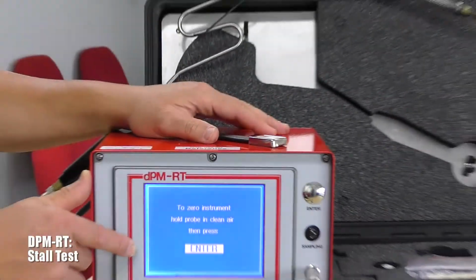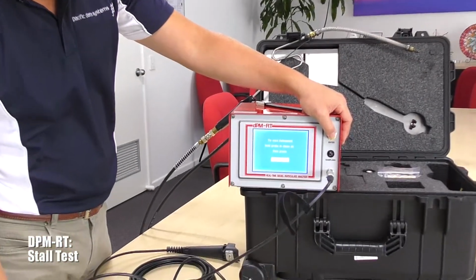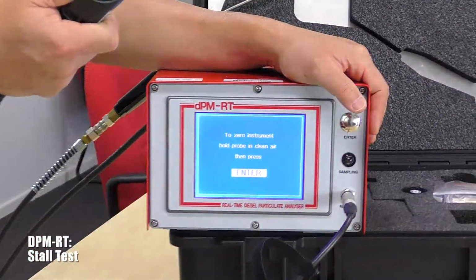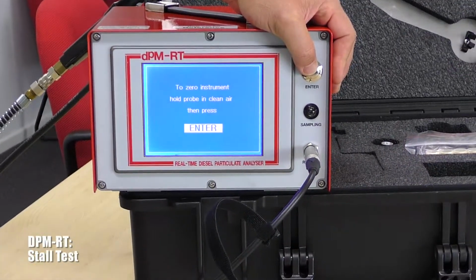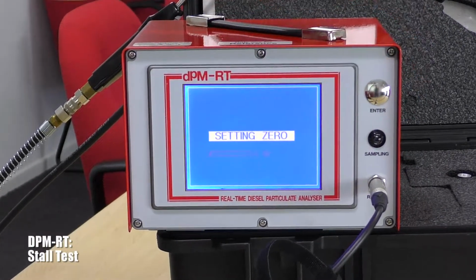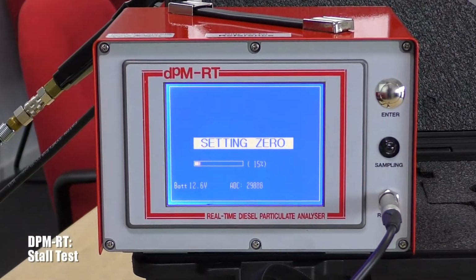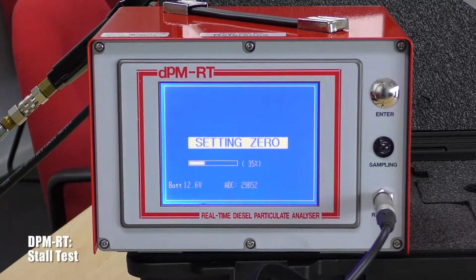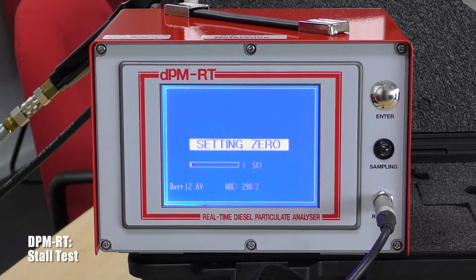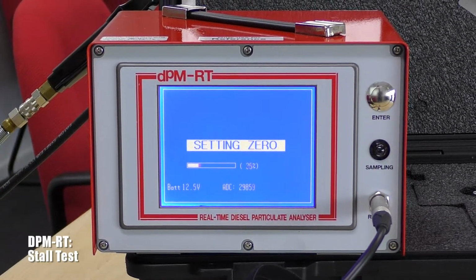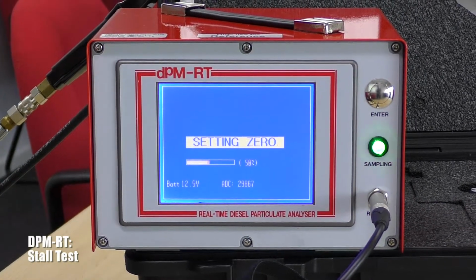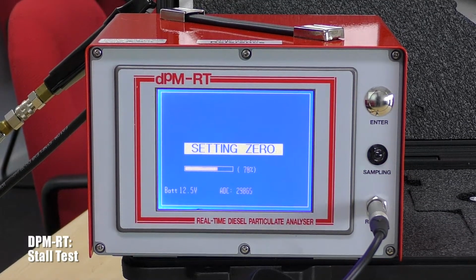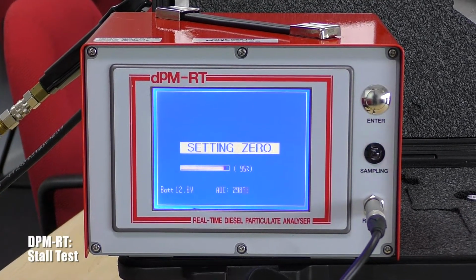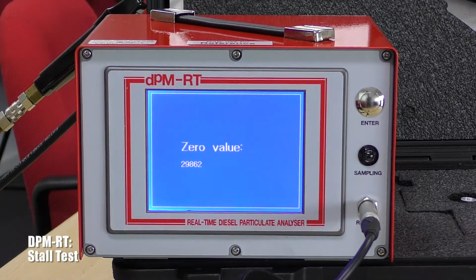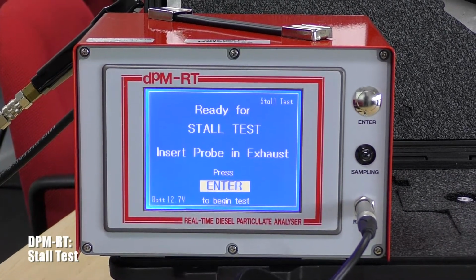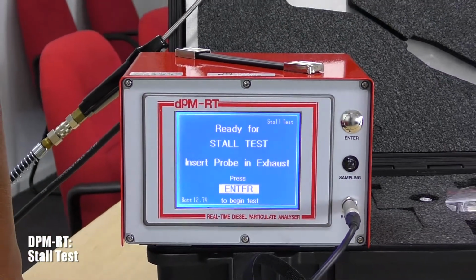Place the probe in clean air, select enter using the remote control or directly through the enter button on the front of the instrument. Again, you'll see the 0 setting bar increase, and it may come back to 0 if the instrument is not happy with the 0 result. The instrument will tell you when it is ready to conduct the test.